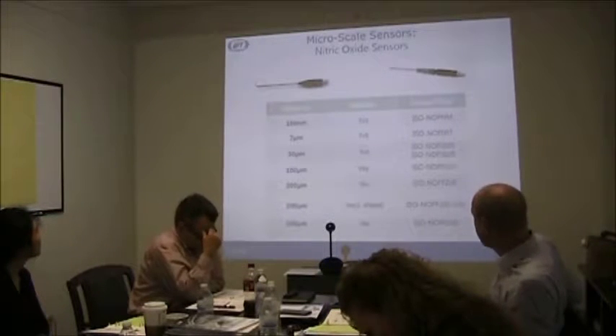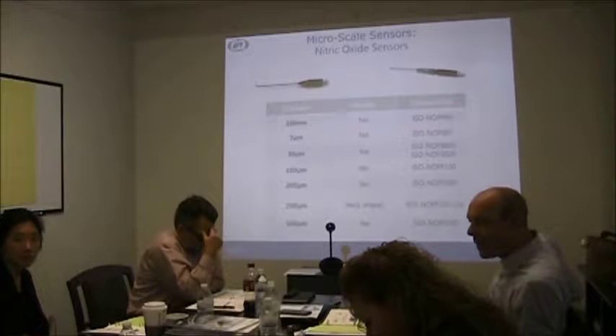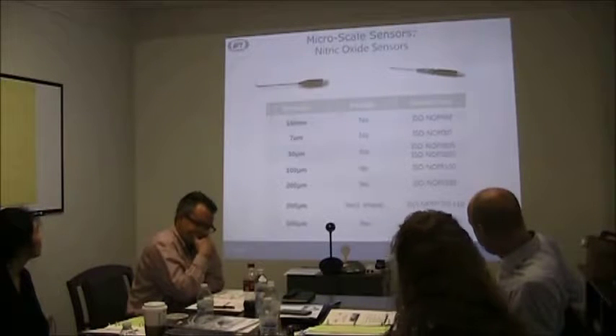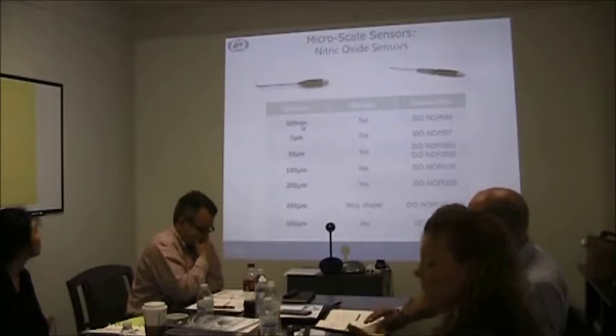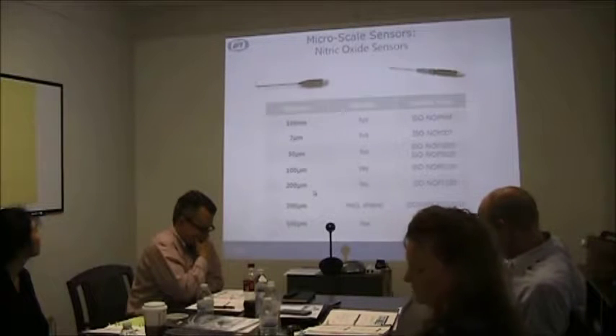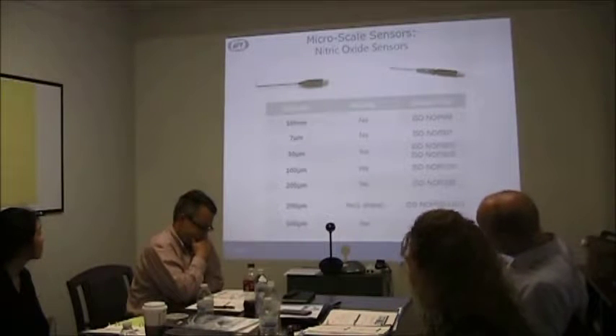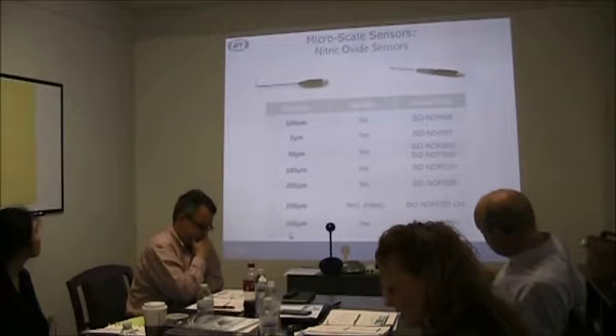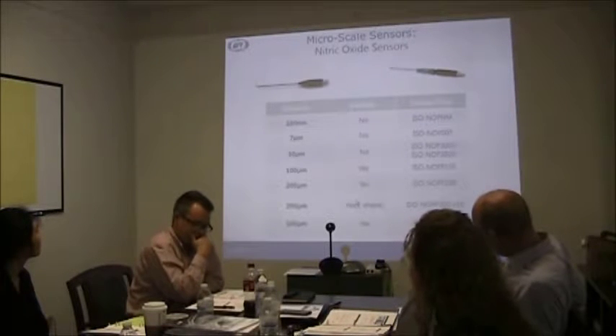Moving along. These are our microscale sensors. This page is specifically nitric oxide. We offer a lot of different nitric oxide sensors, different lengths, different diameters. The left column is your diameter, going from the smallest diameter, which is a 100 nanometer tip, all the way up to 500 micron. I'll pass this around if anybody would like to see. The 100 nanometer, 7 micron, and 30 micron are not flexible fibers, very delicate tips. Your 100 micron and higher are all flexible. Some of them, like the 200, are available in an L-shaped configuration.